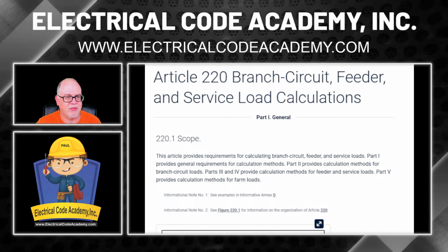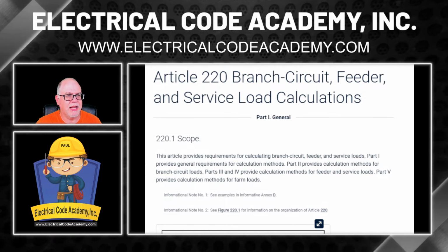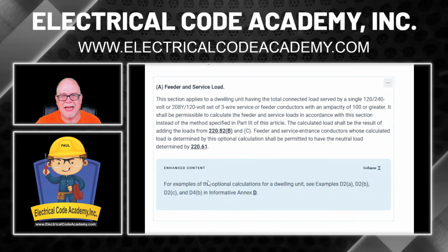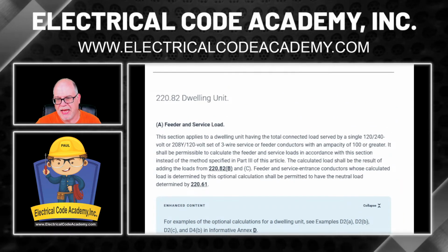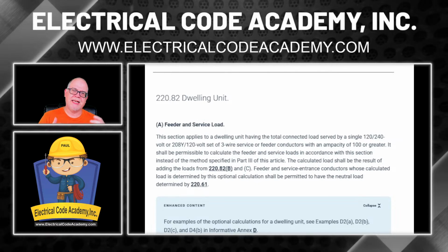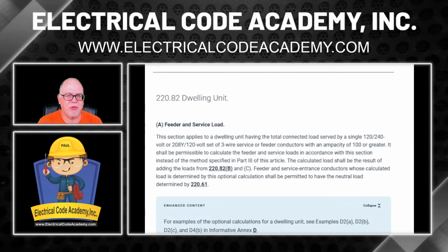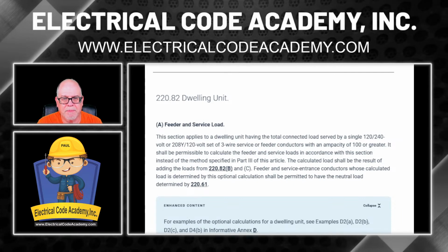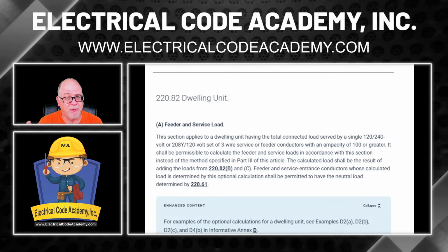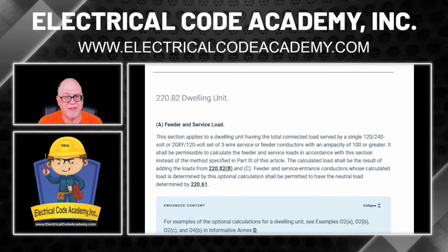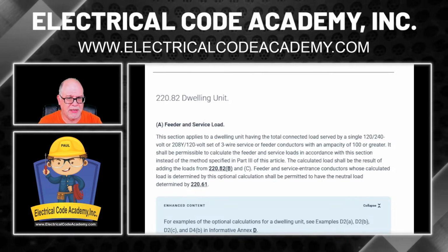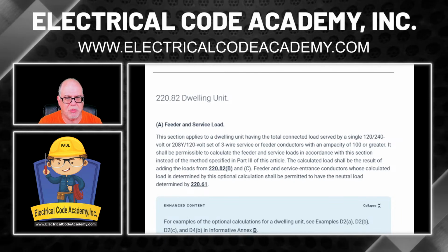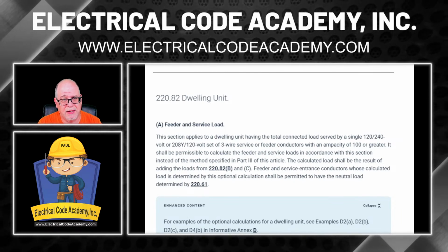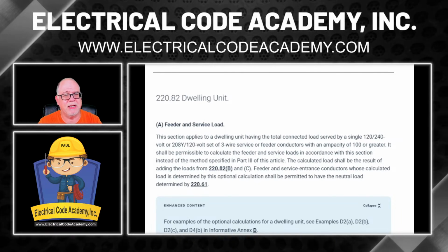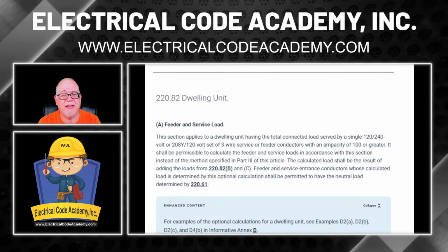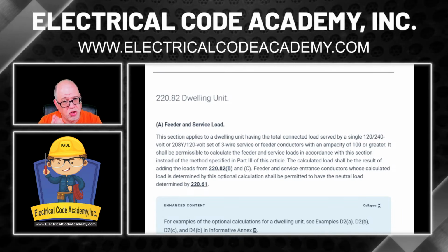Here we're at Article 220 at the very beginning, and I'm going to take us down to where we need to be. And as you know, we're in 220.82. Now, you might be asking, why are we in 220.82? Well, we are doing the optional method. That's Part 4. We wouldn't be in 220.84, in case anybody asks, because that's dealing with multifamily dwellings, and we're not dealing with a multifamily dwelling. We're dealing with a single family dwelling, so we're not dealing with 3 or more. We're dealing with 1. That's why we're in here, and that's why this is titled dwelling unit.